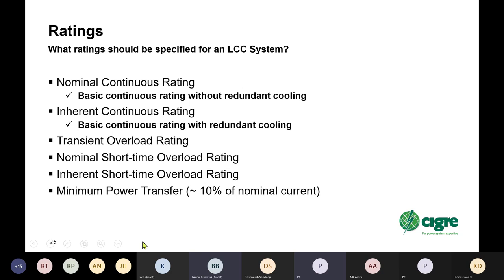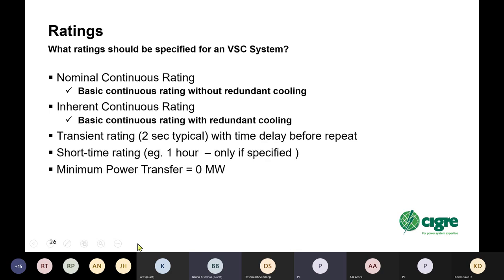And with an LCC, of course, there's a minimum power transfer, approximately 10% of nominal current. And that implies 10% minimum power at full voltage. You can do some tricks like operating the poles at low voltage to get it a bit lower, but typically you can't achieve 0% unless you use ground power. Looking at a VSC system, it's slightly different, but quite similar. Again, you look at nominal continuous rating. That's a basic continuous rating without the redundant cooling. Inherent continuous rating, again, the basic continuous rating with redundant cooling.